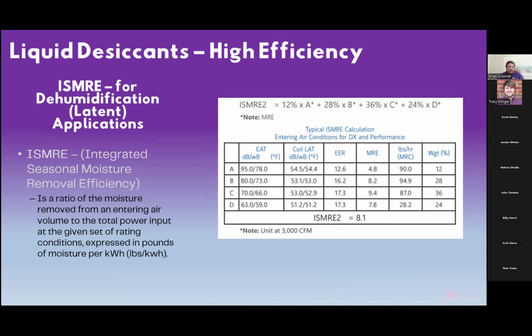ISMRE2 is where we currently are, a slightly different ratio. So we're looking at about 12% of A, 28% at B condition, 36% at C condition, and 24% at D condition. As you can see over here, A, B, C, D, what the conditions are. The most energy efficient condition is 70-66. However, the highest moisture removal capability is at 80-73. So again, we're going to take a blend or a ratio of these to come up with an ISMRE2 value.